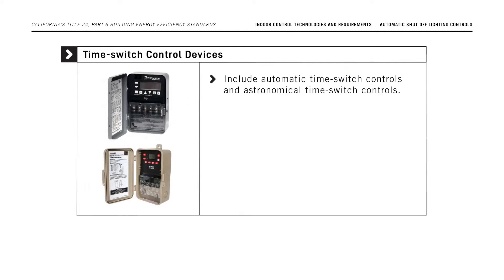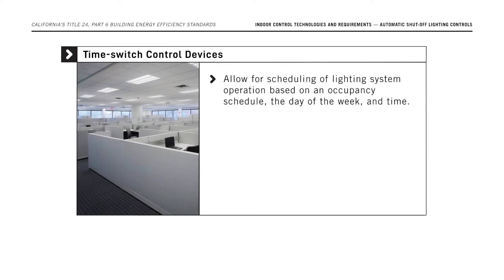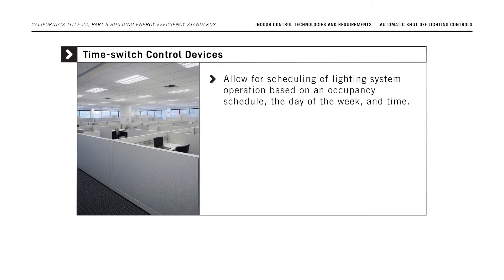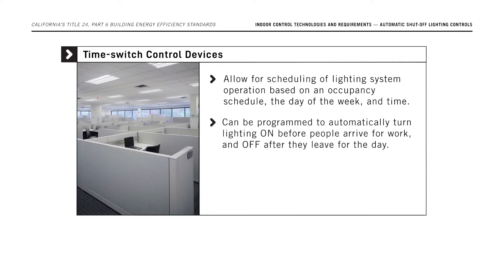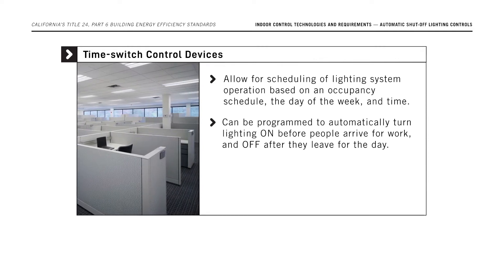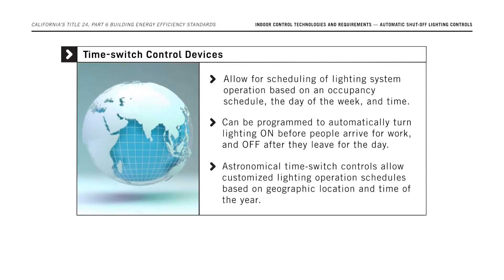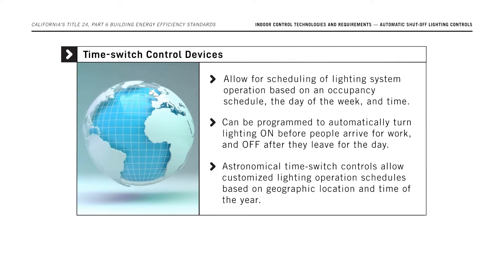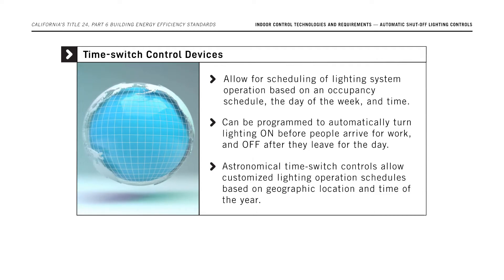Time-based control technologies include automatic time switch controls and astronomical time switch controls. Time switch controls allow for scheduling of lighting system operation based on an occupancy schedule, the day of the week, and time. A time switch control can be programmed to automatically turn lighting on before people arrive for work and off after they leave for the day. Astronomical time switch controls also allow customized lighting operation schedules based on geographic location and time of the year.